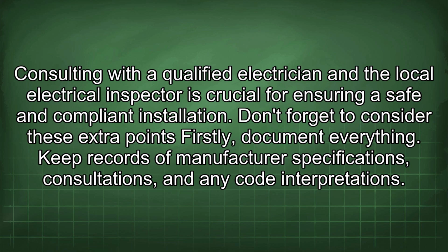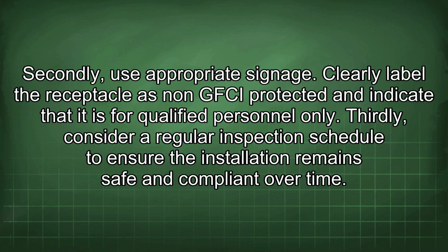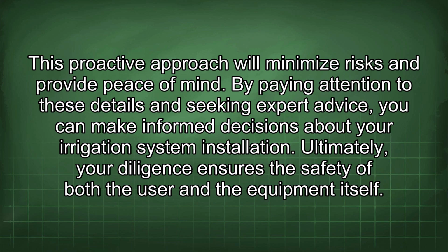Firstly, document everything. Keep records of manufacturer specifications, consultations, and any code interpretations. Secondly, use appropriate signage. Clearly label the receptacle as non-GFCI protected and indicate that it is for qualified personnel only. Thirdly, consider a regular inspection schedule to ensure the installation remains safe and compliant over time. This proactive approach will minimize risks and provide peace of mind.